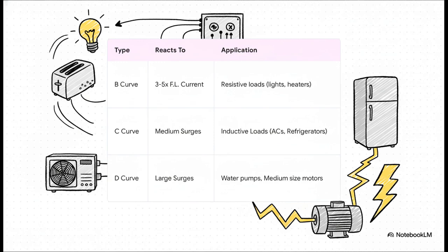But not all circuit breakers are the same. They're chosen specifically for the job they need to do. A B-curve breaker is very sensitive, perfect for simple things like lights. A C-curve is built to handle the medium power surge from a device like a refrigerator kicking on. And for something really heavy duty, like a water pump with a huge startup surge, you need a tough D-curve breaker. It's all about matching the protection perfectly to the device.